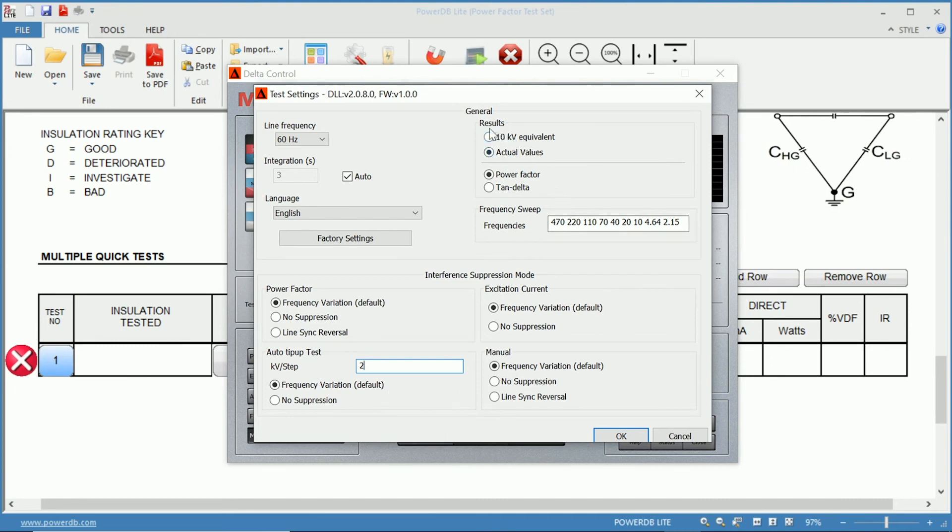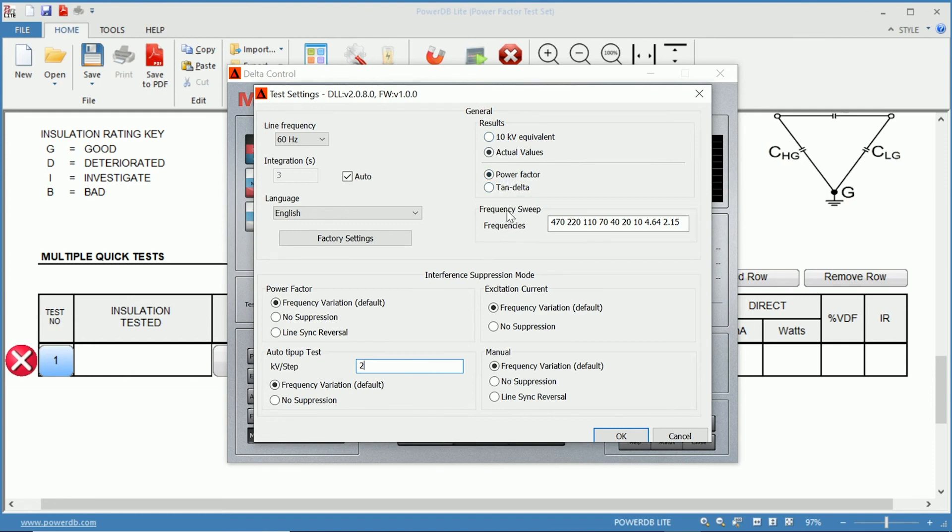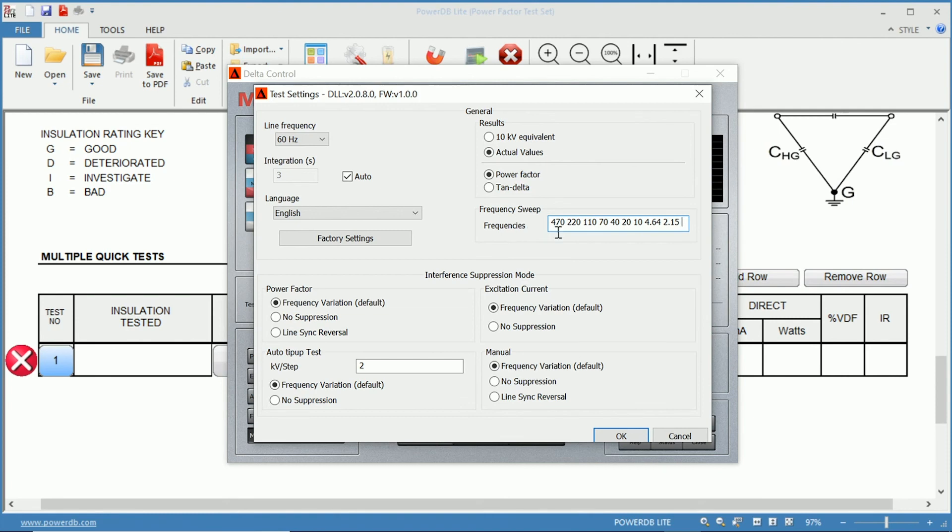You can get your results in the actual values, which are the values that you measure, or you can set them to your 10 kilovolt equivalent. You can get your results on either power factor or tan delta. And frequency sweep. This is the narrowband DFR. You can sweep between the 500 and 1 hertz with the default values that are chosen, or you can choose to add or change these frequencies as well.